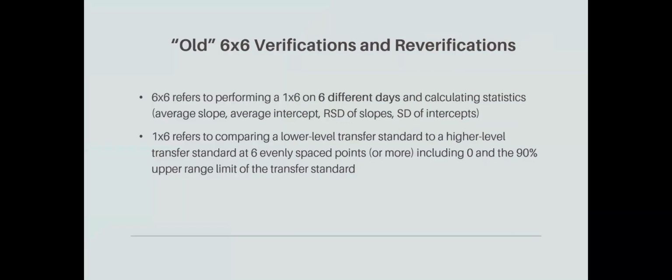6x6 verifications, if you're not familiar, are referring to these 1x6s that are done on 6 different days and then calculating relevant statistics. And that 1x6 refers to comparing the lower level transfer standard to the higher level transfer standard at 6 evenly spaced points or more, including 0 and basically 90% of the full scale of the transfer standard. So in order to verify a new or repaired instrument, it would take you at least 6 days. They don't have to be consecutive days, but it would take you at least 6 days to go through the verification process.